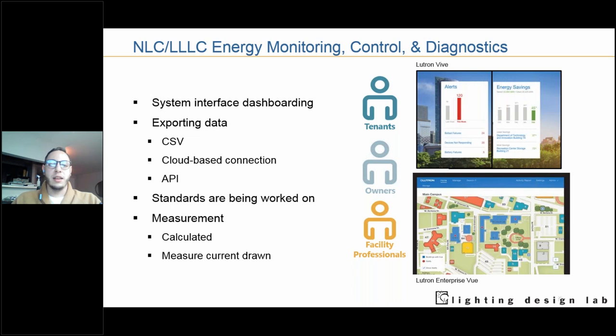Two main ways that energy monitoring is being done today: calculated, meaning you input the wattage of the lamp and the system has an internal matrix where if you reduce the light by a certain percent, it calculates the savings. The more precise and increasingly standard approach is actual measurement of current draw, where some load controllers have additional wires just to measure the current depending on the voltage and report on the energy that way. That is a more popular way to monitor energy these days.